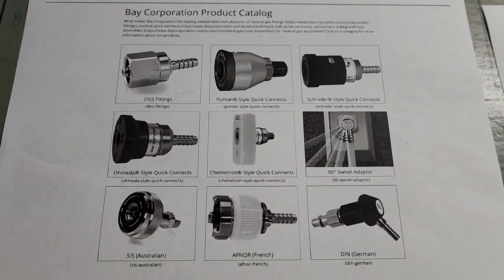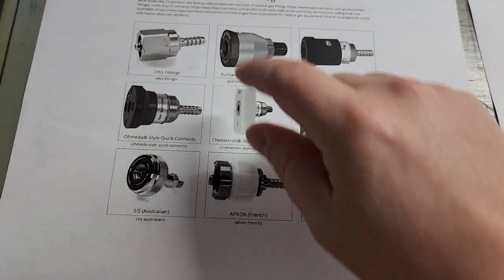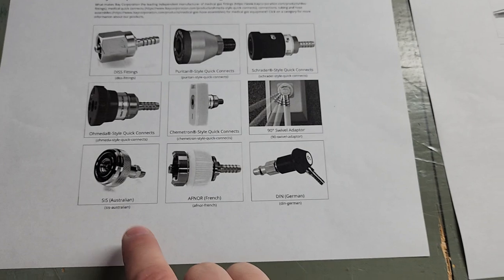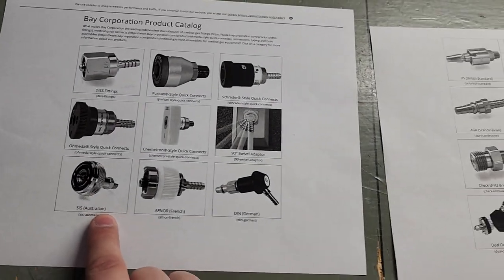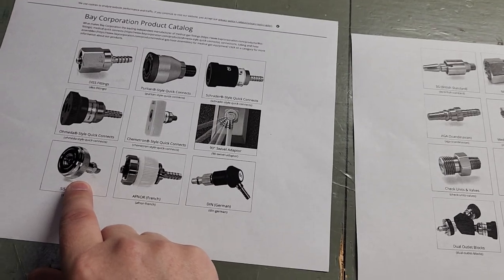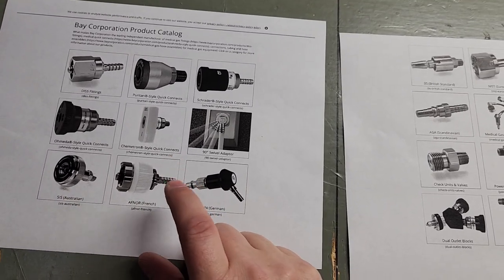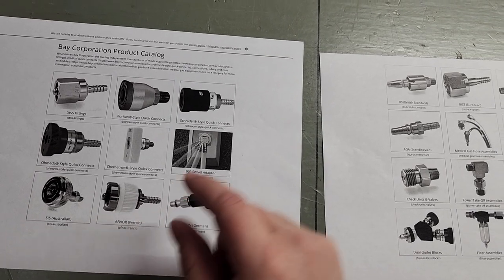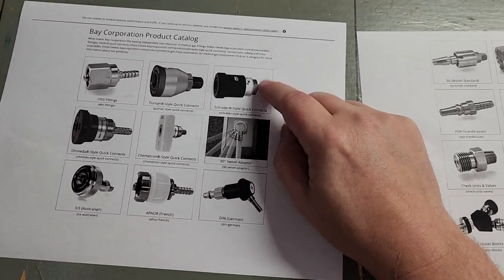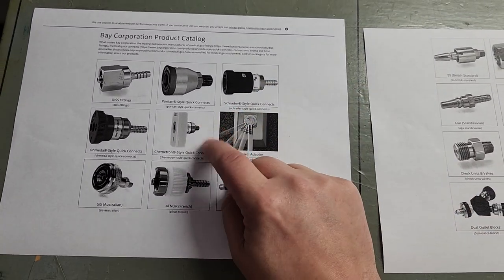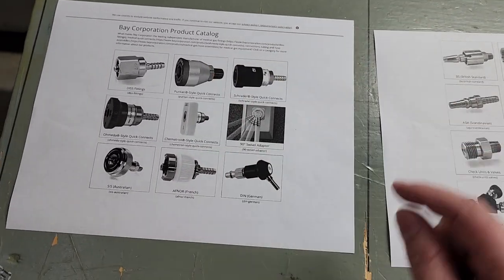Some of these fittings you'll see very commonly: DISS fittings, Ohmeda fittings—a lot of hospitals use those. Some use the stainless steel that comes on European equipment. Schrader style—a lot of hospitals still use that, it's an older style. Chemetron, Puritan—you might see those.